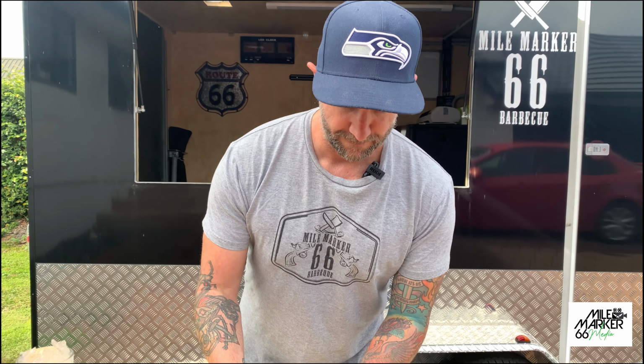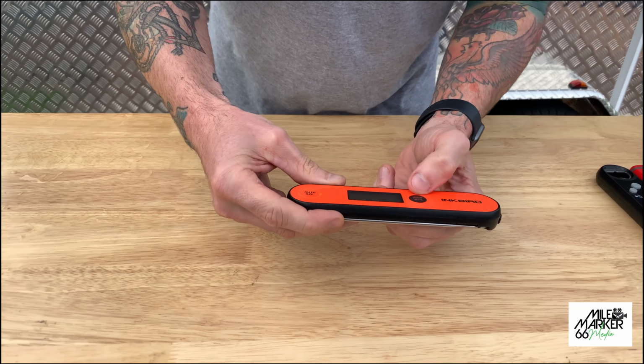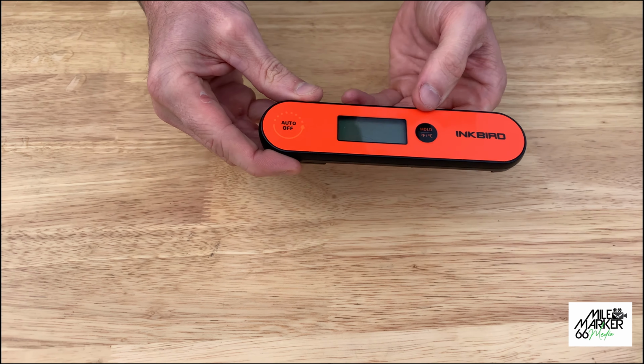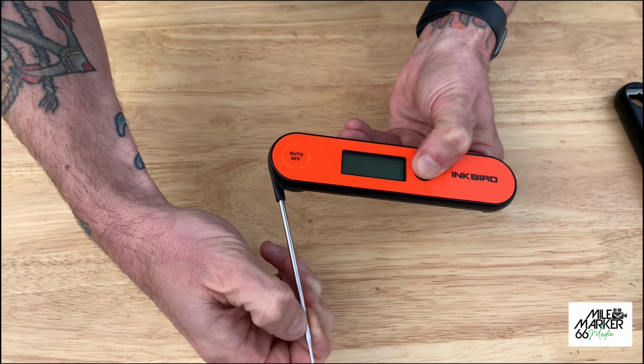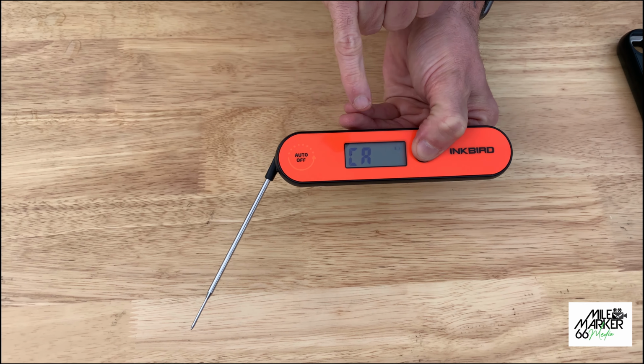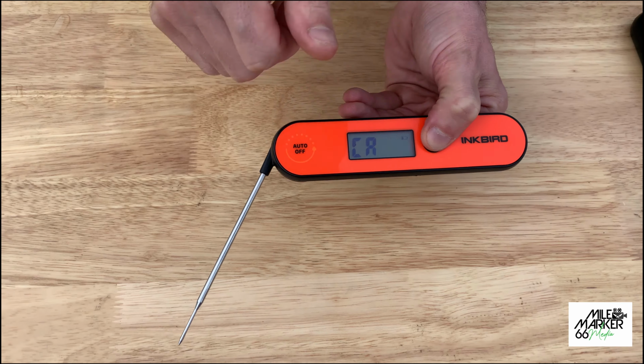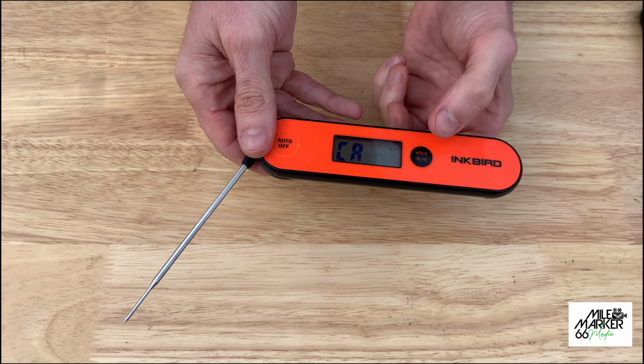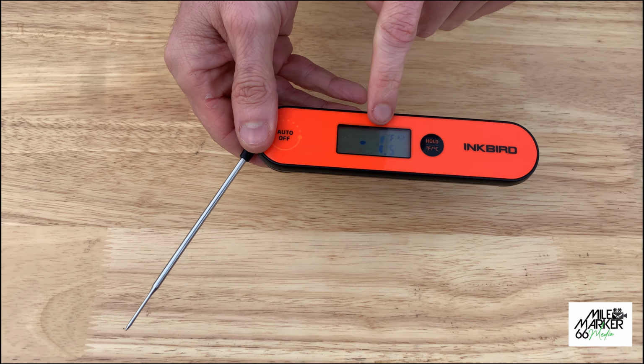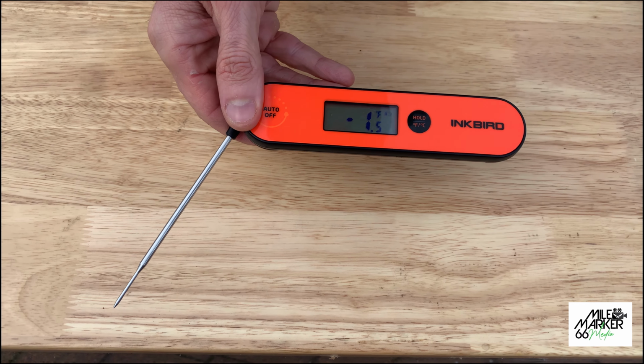Now, carrying out a calibration on an Inkbird is pretty straightforward. You can check out the manufacturer's instructions, but I'll take you through it. What we need to do is hold down this button and ensure that your probe is closed and the display is off. We hold down our button, and while you've got it held down, open up the probe. What that's going to do is bring up a display that says CA for calibration. That's calibration mode. And we click it again, and you're going to get a display start flashing.